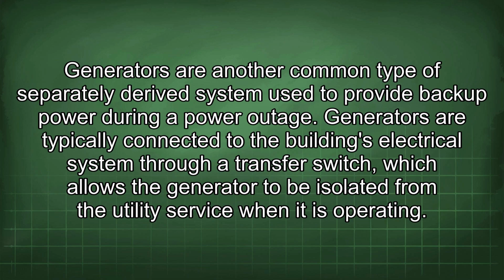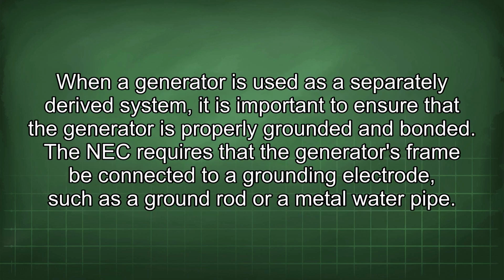Generators are another common type of separately derived system used to provide backup power during a power outage. Generators are typically connected to the building's electrical system through a transfer switch, which allows the generator to be isolated from the utility service when it is operating. When a generator is used as a separately derived system, it is important to ensure that the generator is properly grounded and bonded. The NEC requires that the generator's frame be connected to a grounding electrode, such as a ground rod or a metal water pipe.